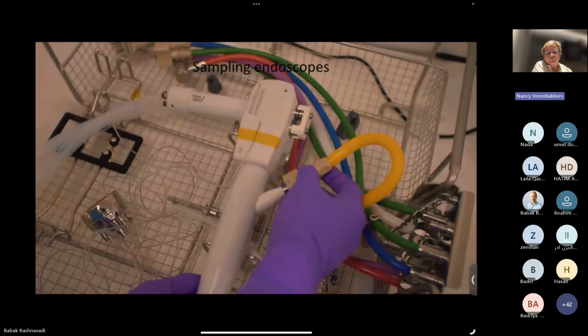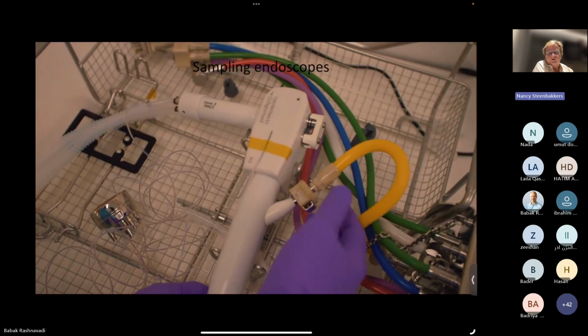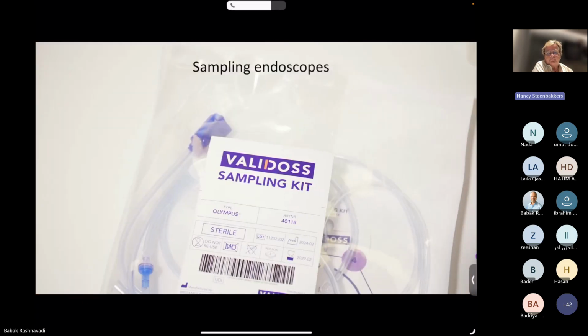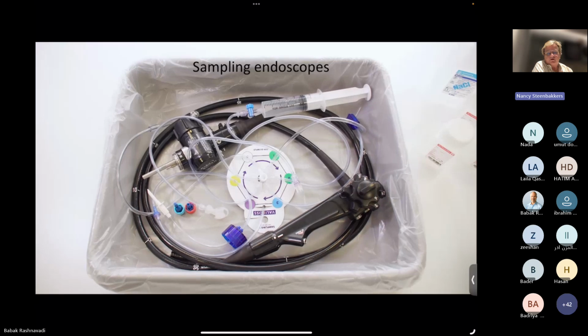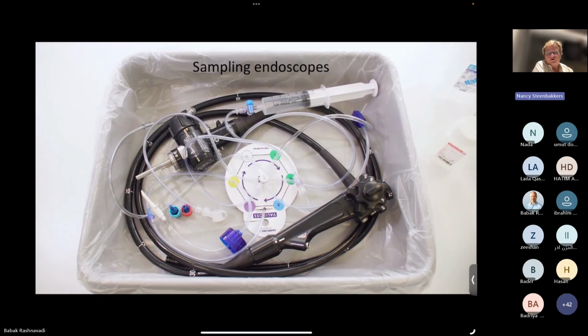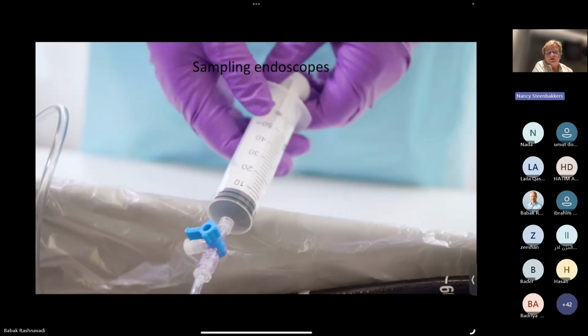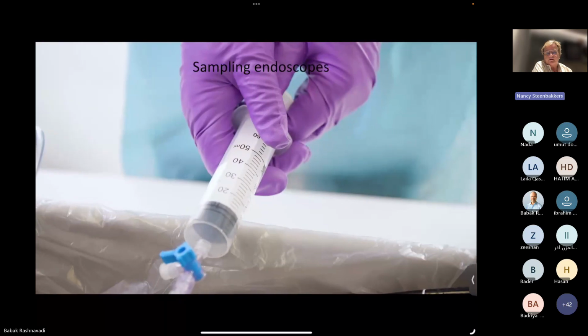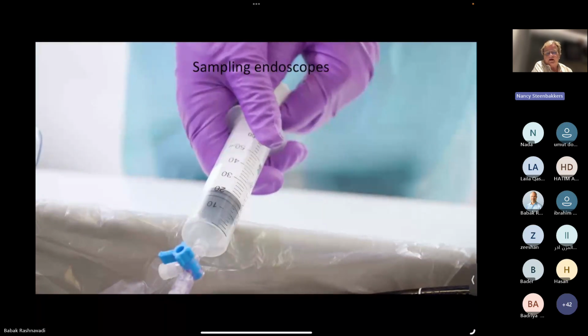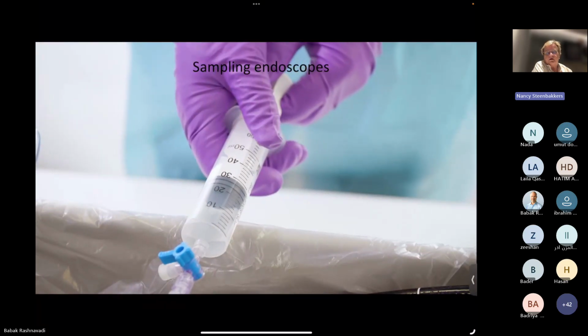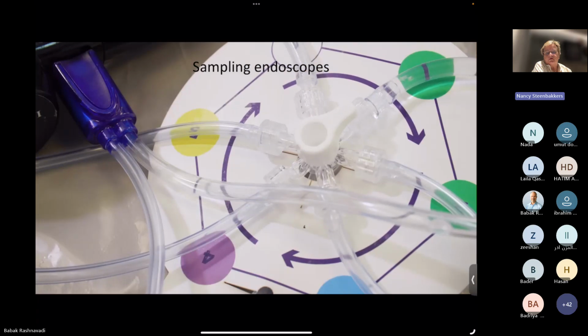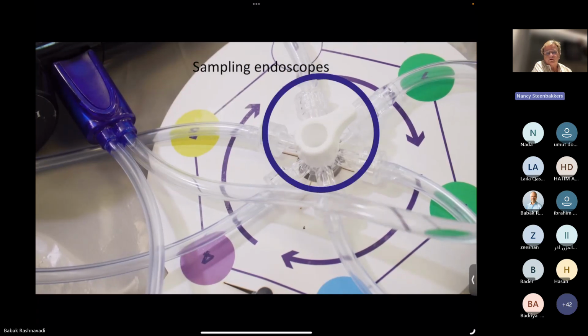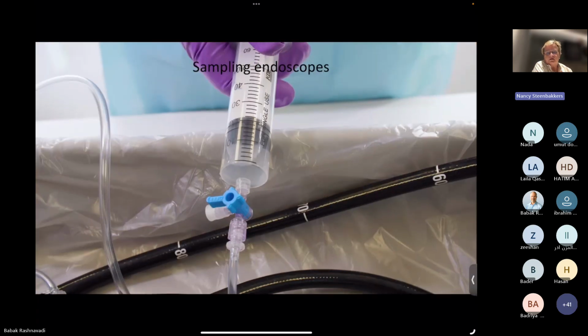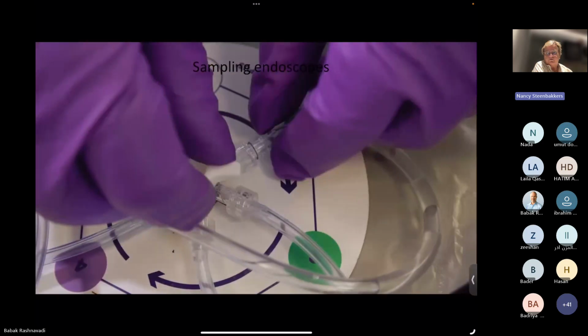You can see here the introduction when the endoscopes are getting into the washer disinfector. But after the washer disinfector, you can sample your endoscopes, and you can also do the sampling after your pre-cleaning with your sink. In my idea, it should be good that you do it once a week or once a month to see if your pre-cleaning is still in a stable condition or not.